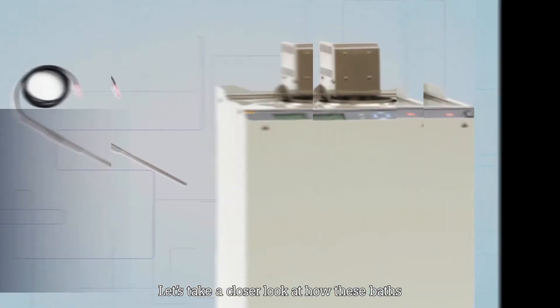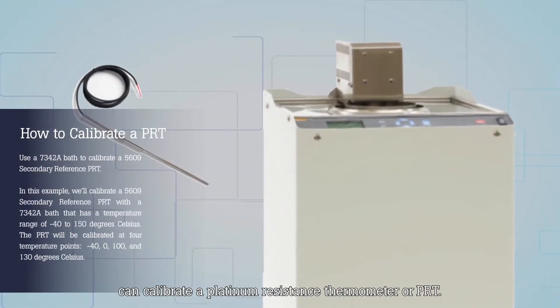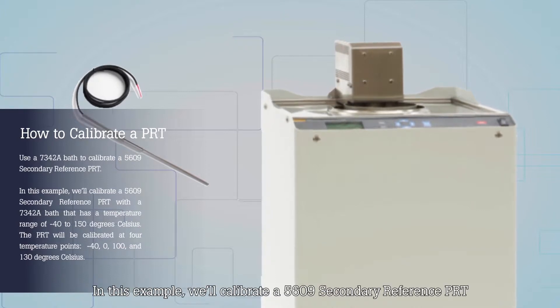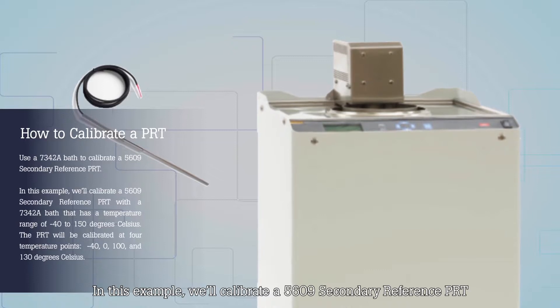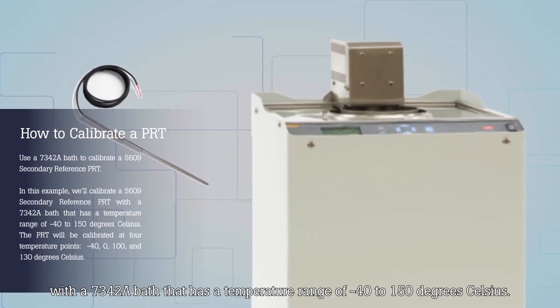Let's take a closer look at how these baths can calibrate a Platinum Resistance Thermometer or PRT. In this example, we'll calibrate a 5609 secondary reference PRT with a 7342A bath that has a temperature range of minus 40 to 150 degrees Celsius.